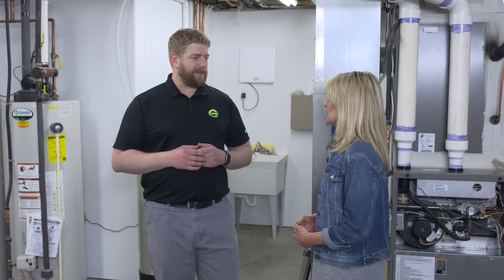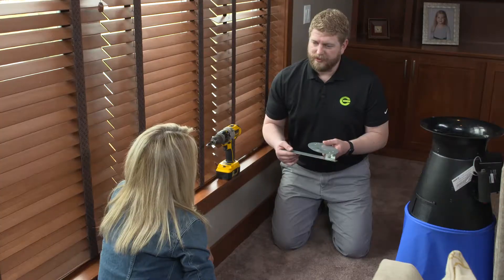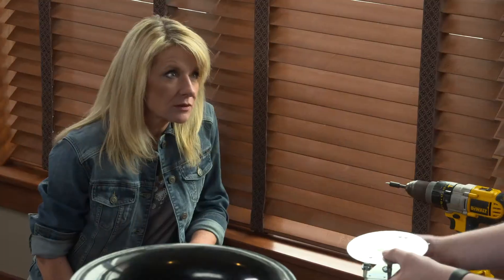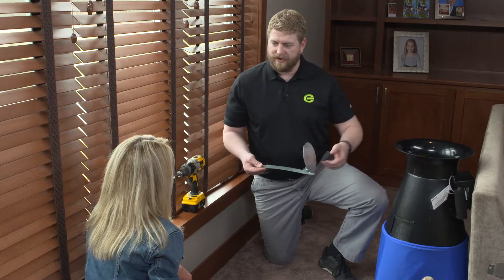So Silas, what's the last thing you need to do here? After we've made all the repairs to the heating and cooling system, the last step is to air balance — essentially taking air from rooms that have too much and redistributing it to rooms that don't have enough. We're going to do that by installing manual balancing dampers. We use what we call a retrofit damper — it literally just slides into each of the registers that have too much air, gets fastened with one sheet metal screw, and then I can adjust the damper to redirect airflow back to a different duct.